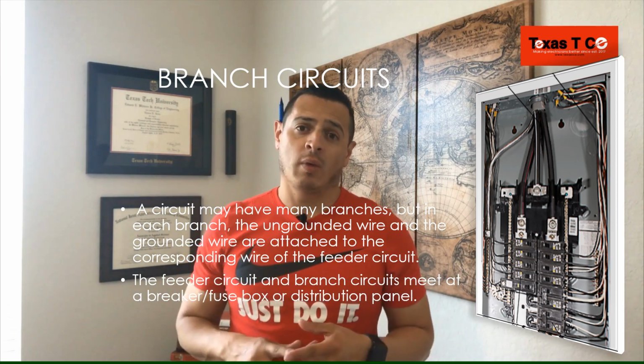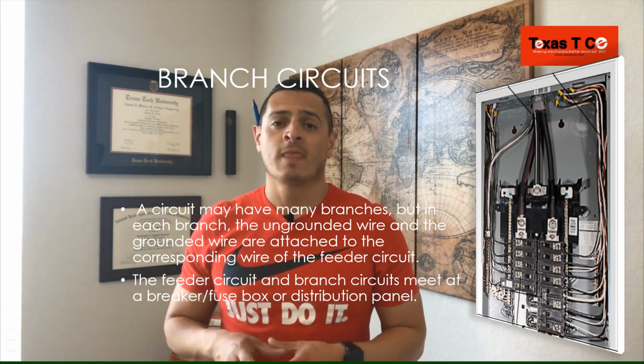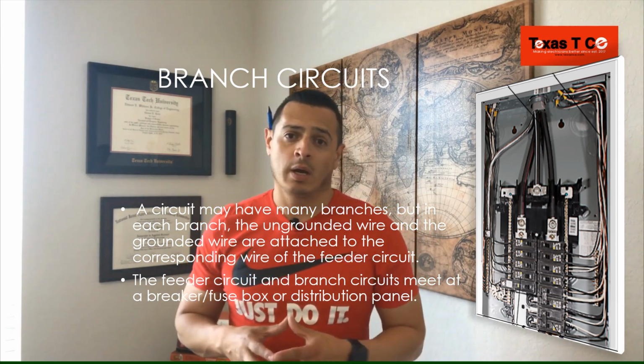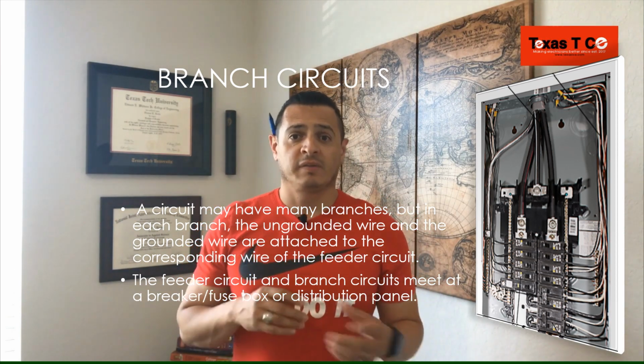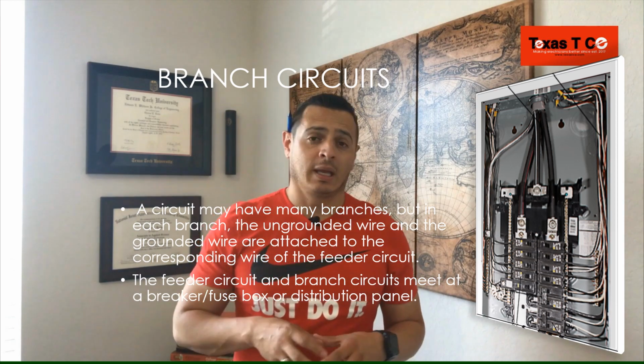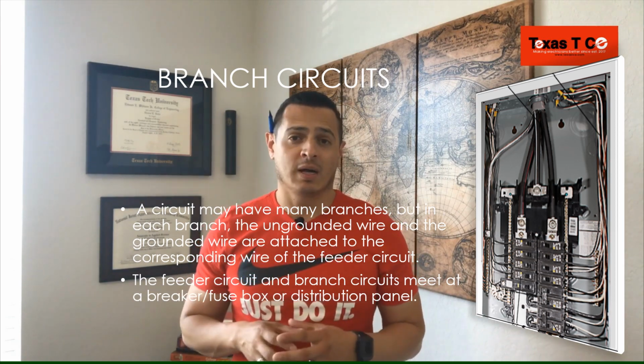This is going to bring us to some branch circuits. The circuit may have many branches, but in each branch, the ungrounded wire and the grounded wire and the grounding wire are all attached to the corresponding wire of the feeder circuit. The feeder circuit and the branch circuits meet in typically a breaker or fuse box or distribution panel.